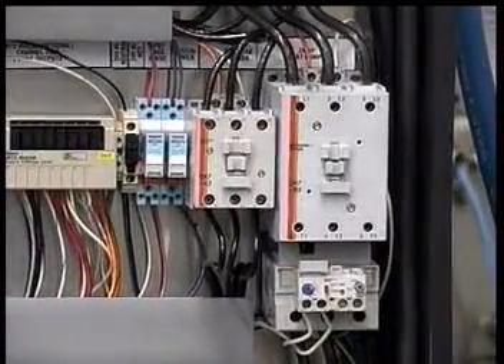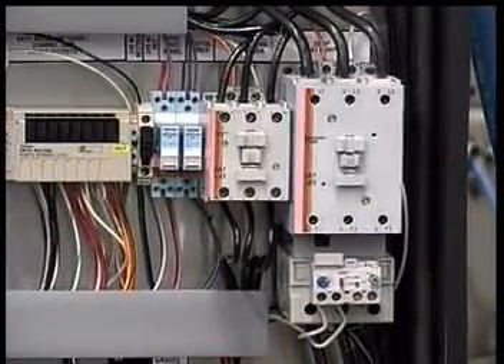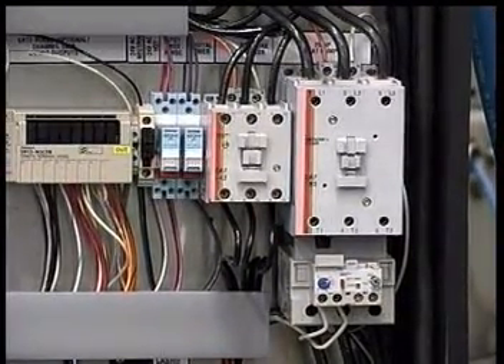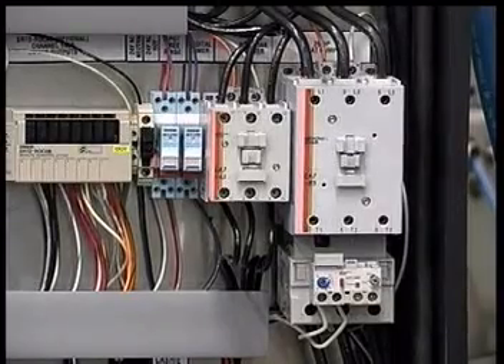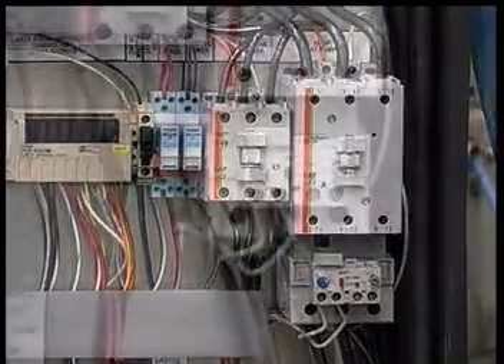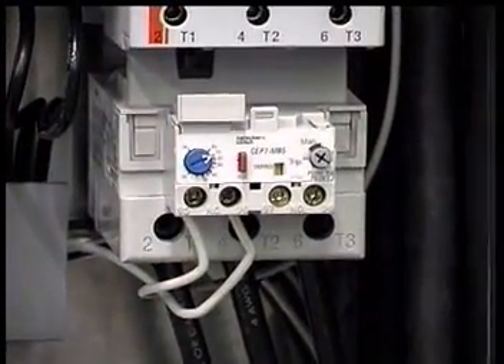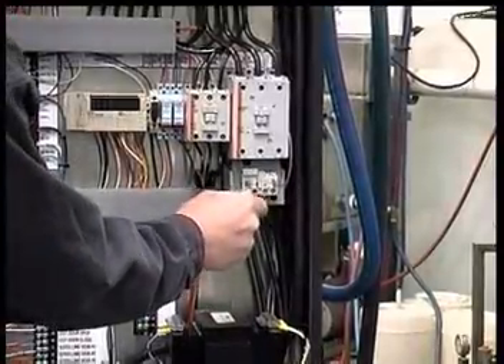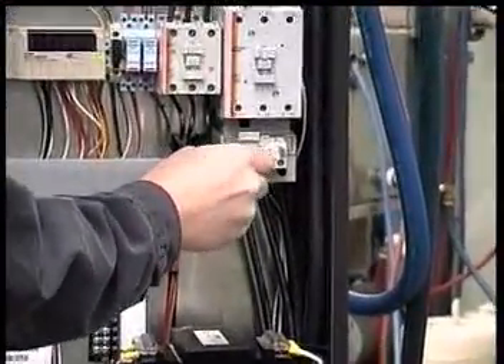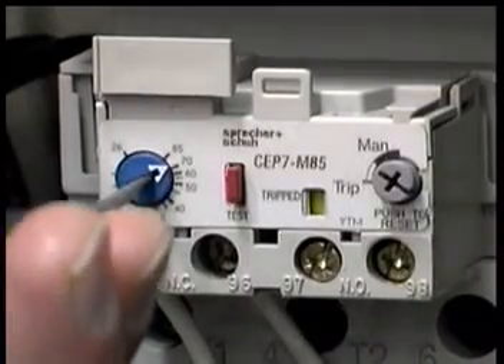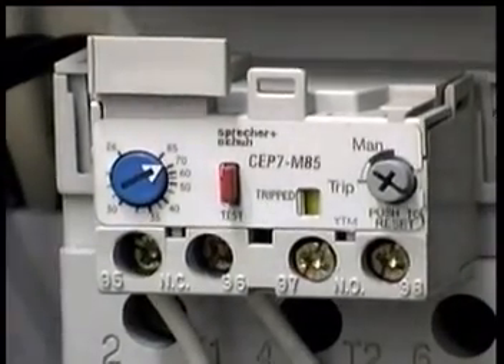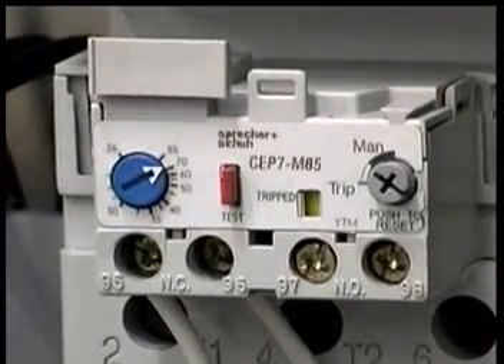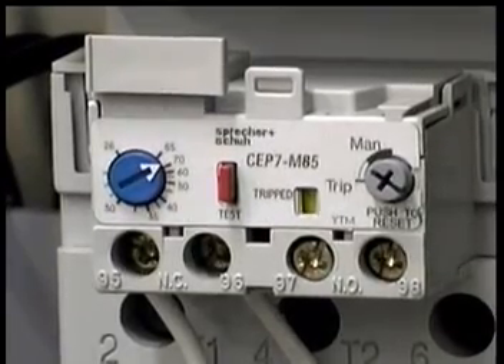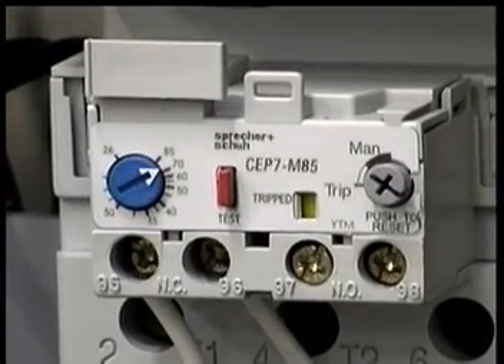The CAT 3535 motor starter is mounted on the right-hand side of the electrical control panel. Motor starters typically offer very little maintenance requirements. There is a safety overload with the starter. The overload should be set at 70 amps when operating with 208 voltage. Should there be excessive amperage, the overload will trip and need to be reset. The starter will not engage and therefore the pump motor will not run if the motor starter overload is tripped. When tripped, a yellow flag appears in the tripped window.